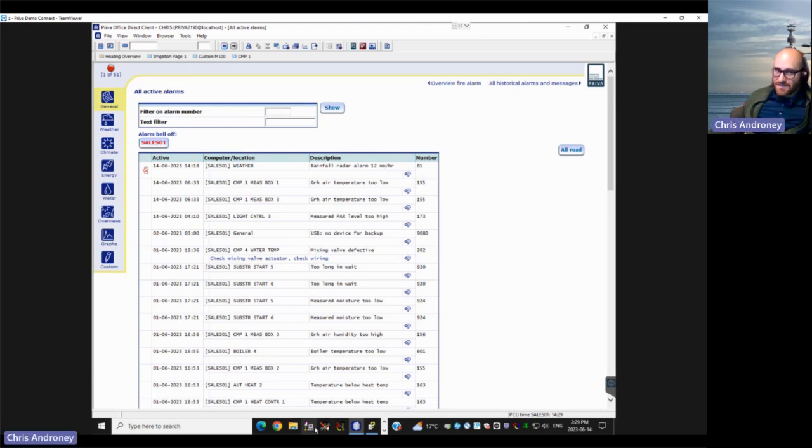In each of the Priva systems, typically in your CPC panel, in your main panel, you'll have an alarm board. What the alarm board does is there's 4 contacts on it. So you can send an alarm, and what it does is it sends a dry contact, just a relay contact for alarm level 1, alarm level 2, alarm level 3. And then the 4th contact's for any alarm, send a message out.